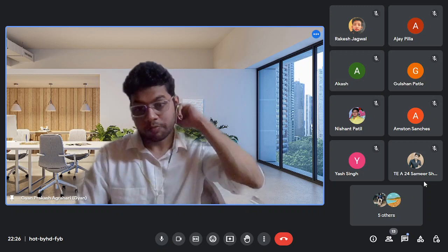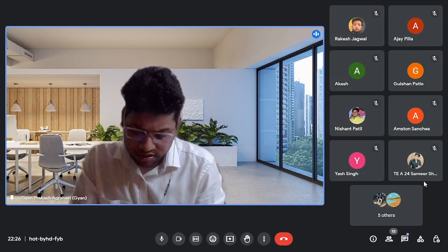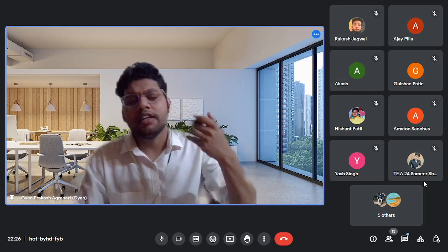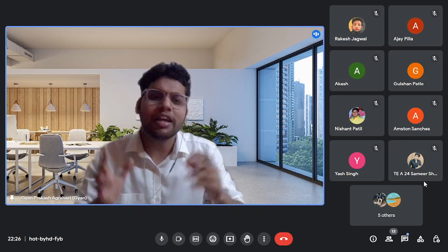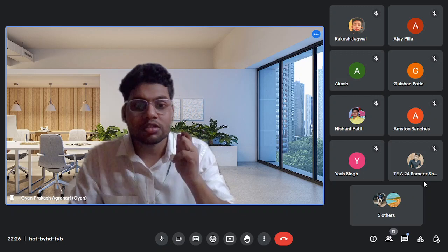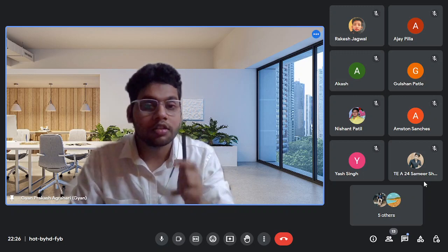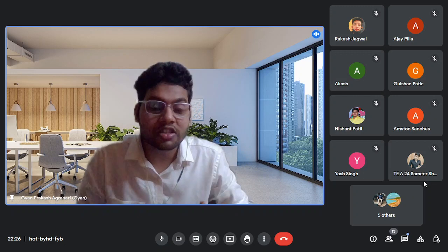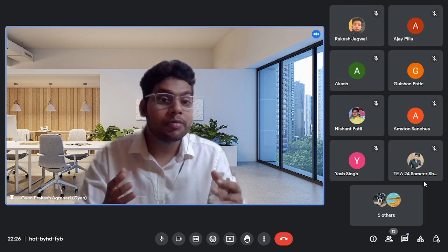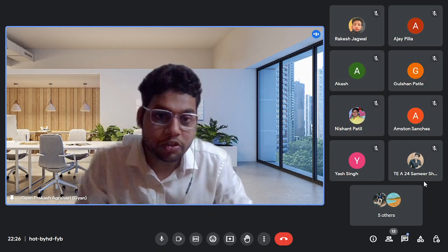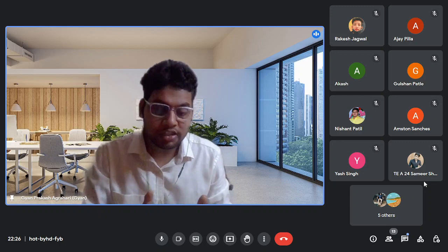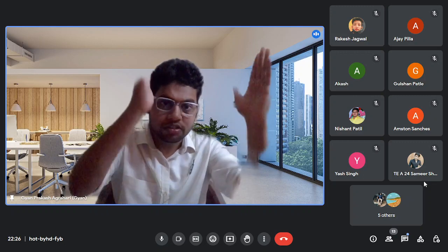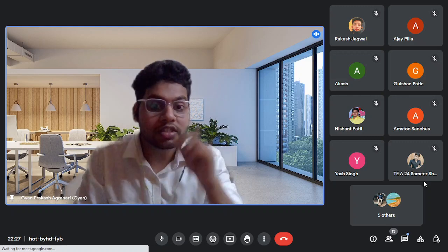All right, so let me tell you this. Whenever this type of question comes, and you know the reasons that it involves the equation of continuity, the energy conservation principle, and many things to explain the whole mechanism, your attention should be on first telling the exact reason and then explaining how discharge pressure is created in the centrifugal pump. It is because of the design of the volute casing of the centrifugal pump. The volute casing is designed in such a way that its volume, or its cross-sectional area, keeps on increasing. Due to this, discharge pressure is created.